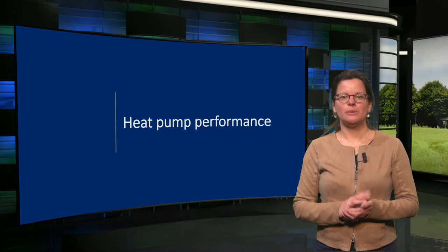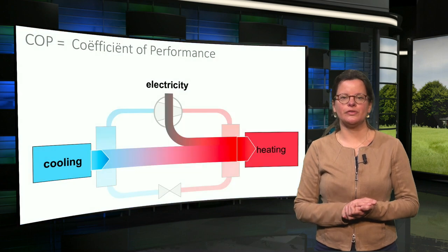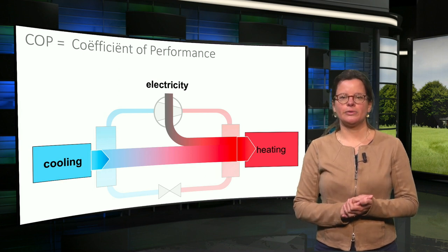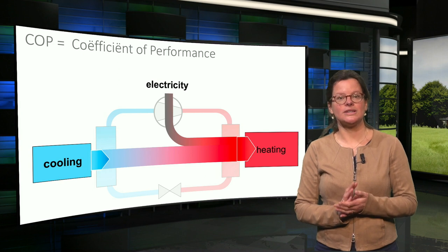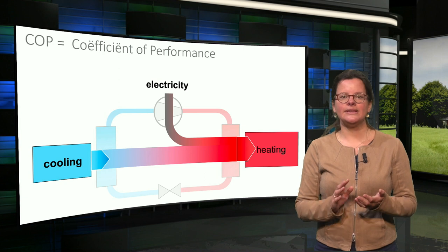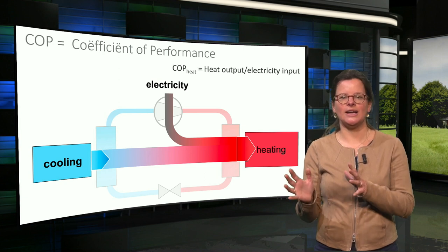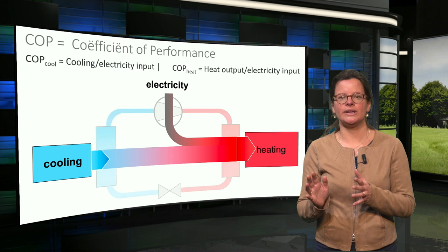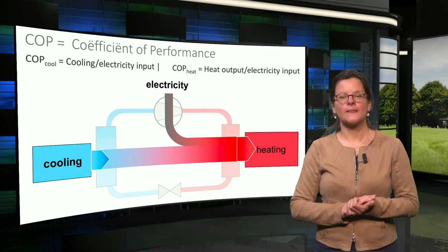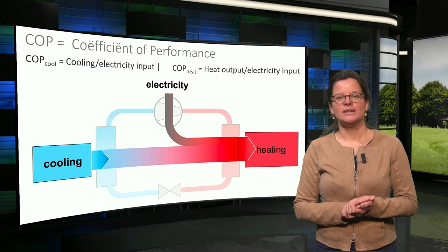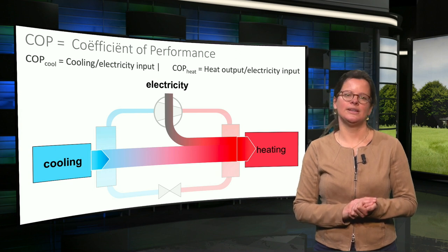Now we will talk about heat pump performance. The heat pump performance is referred to as the COP, the coefficient of performance. In the COP, the free environmental heat or cold used is not included — only the amount of electricity needed is considered. The COP for heating is defined as the heat output divided by the electricity input, and the COP for cooling is defined as the cooling achieved divided by the electricity input. Please note that COPs are usually higher than 100%, which is possible since the free environmental heat is not included in the equation.